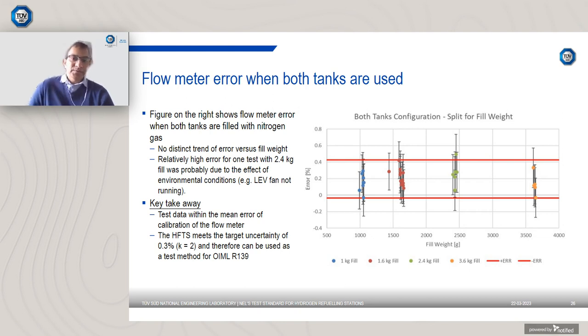But the key takeaway from this graph essentially is that the test data are within the mean error of calibration for the flow meter, and we can essentially say that the test standard meets a target uncertainty of 0.3% and therefore is suitable for use as a test method for OIML R139.